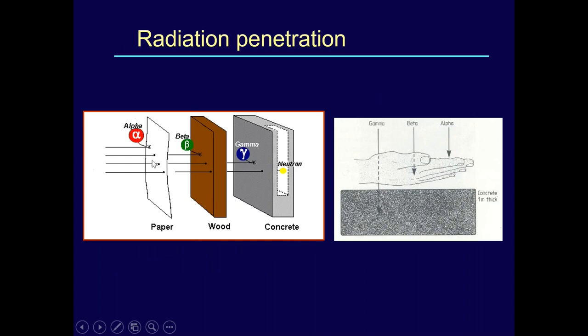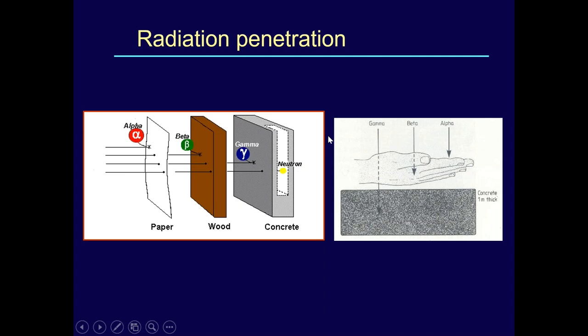Different types of radiation — alpha, beta, and gamma — have different penetrating properties. Alpha particles are heavy charged particles that can be attenuated by a thin piece of paper. Beta or electron particles require wood or a perspex material to attenuate. Gamma and X-rays can pass through concrete materials, and high-energy X-rays interacting with high-density materials like steel can produce neutrons. High-energy X-ray machines therefore require neutron barriers to protect workers in the surrounding radiation environment, including radiotherapy, nuclear medicine, and radiology departments within a hospital.